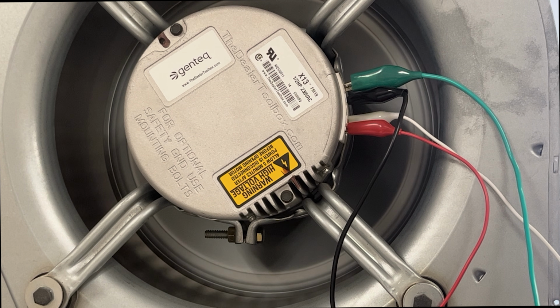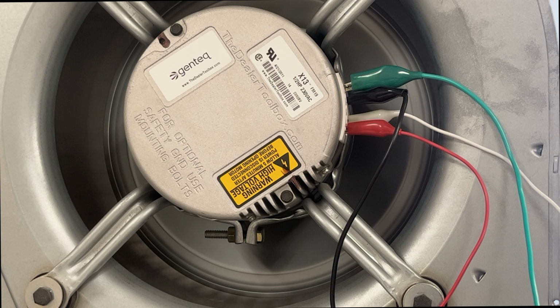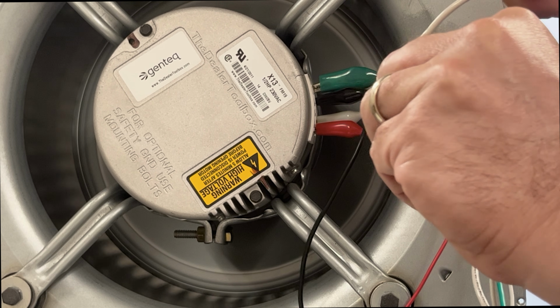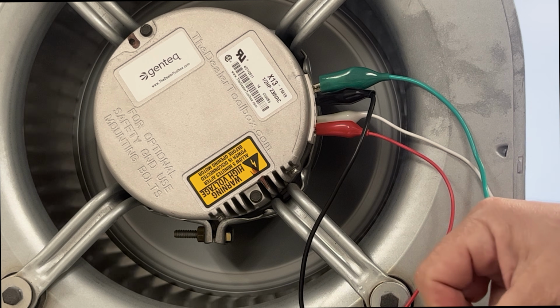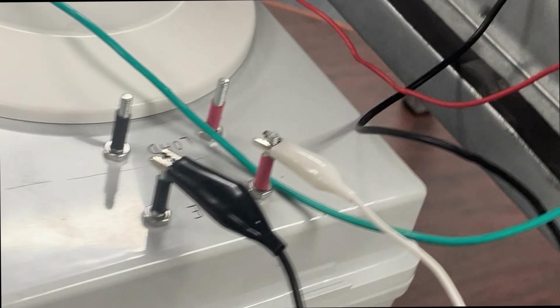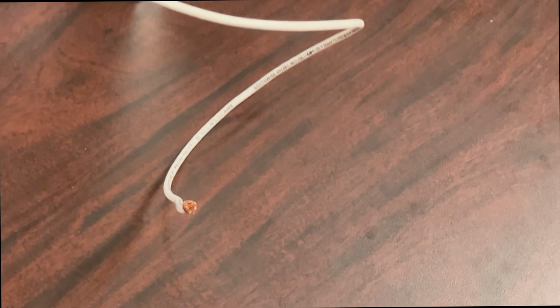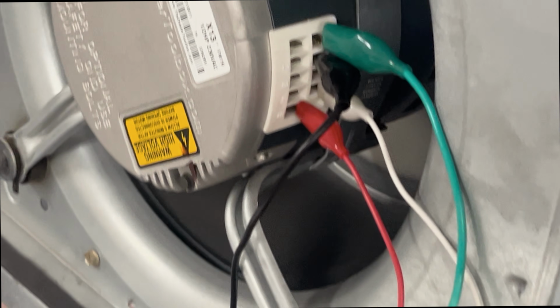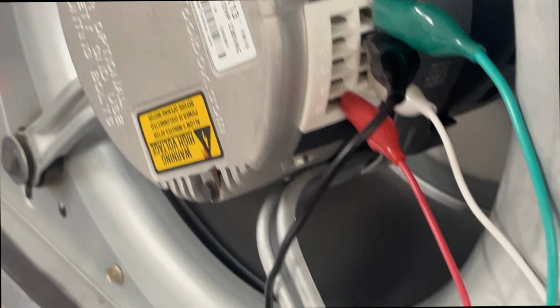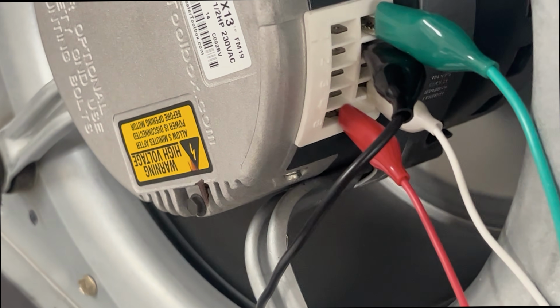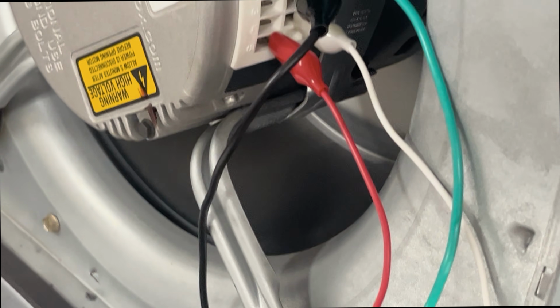All right, so we got the power turned off. All we need to do is take neutral, unhook it, and connect it to line. I'm already wired to 5. We now have 2 legs of power, L1 and L2. We're no longer hooked to neutral. See my white wire just dangling there. Okay, we have green for common. We have red 24 volts going up to terminal 5 for high speed. I have white and black, which is N and L. They're wired to L1 and L2.